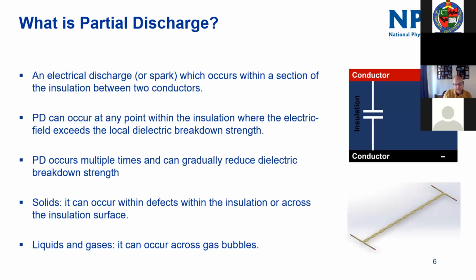One of the issues we're looking to understand better at the moment is a phenomenon known as partial discharge. This is where you don't get to those voltages, you don't get to your 3 kilovolts per millimeter, but you can still get a small electrical discharge or spark occurring within the insulator between two conductors. And particularly where that dielectric is organic based, that can lead you into problems.